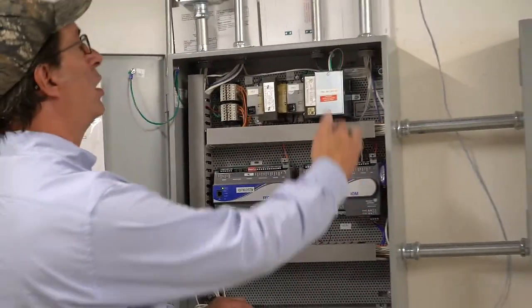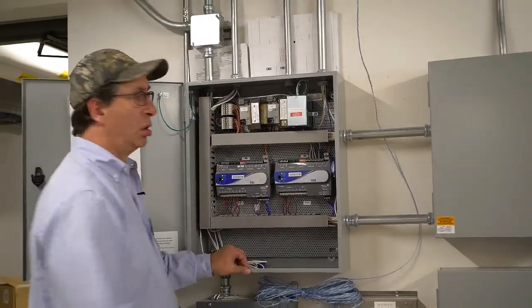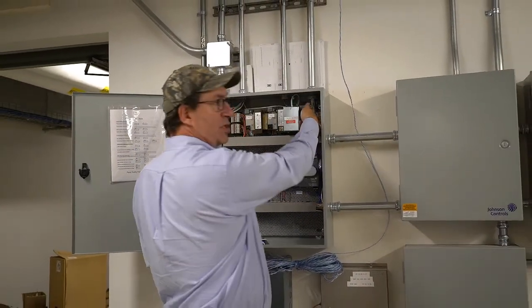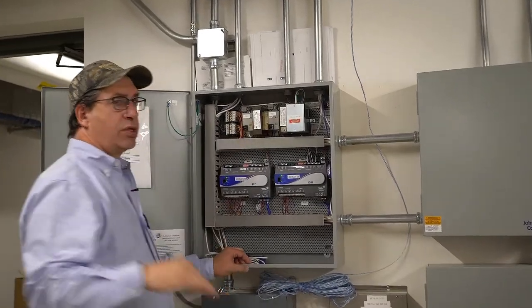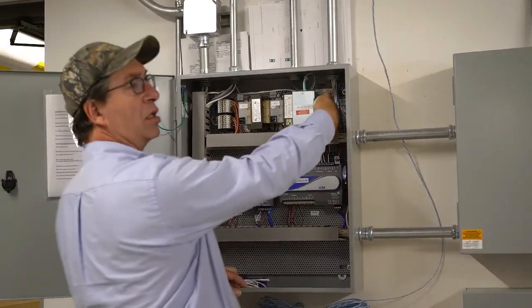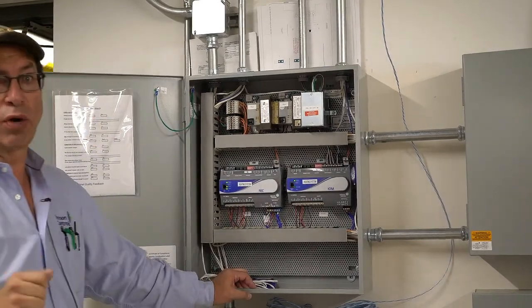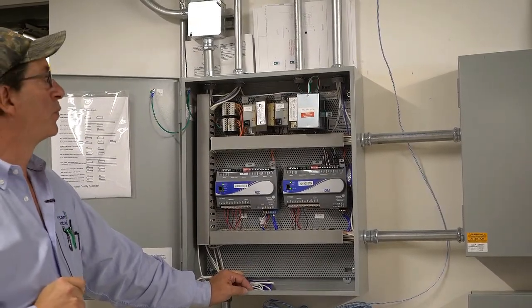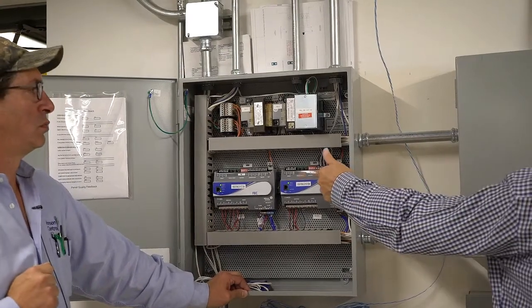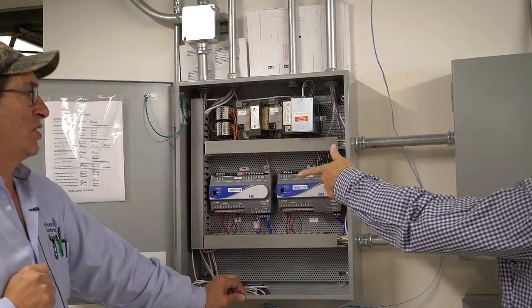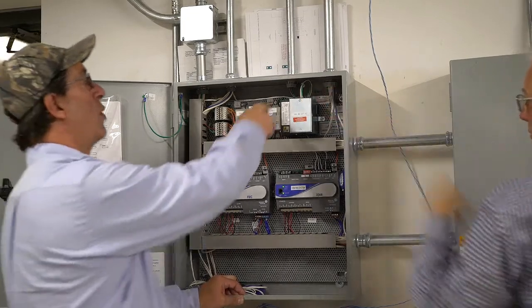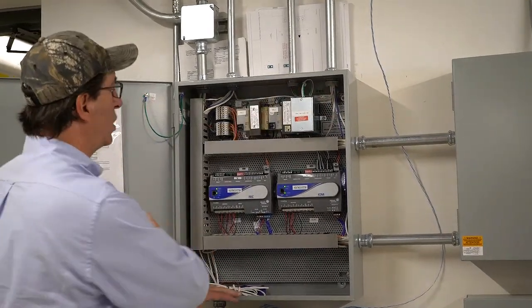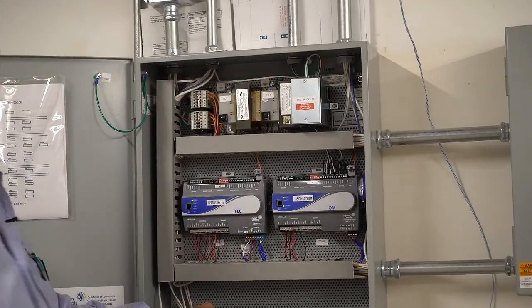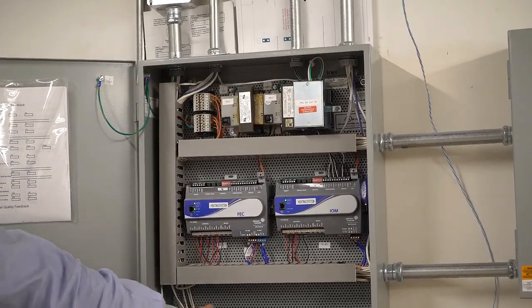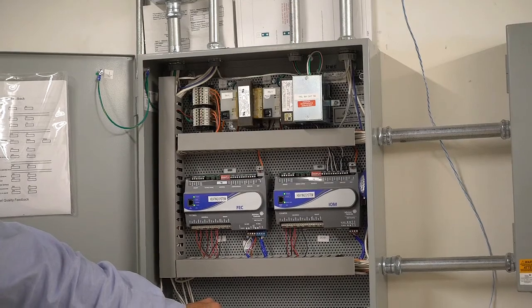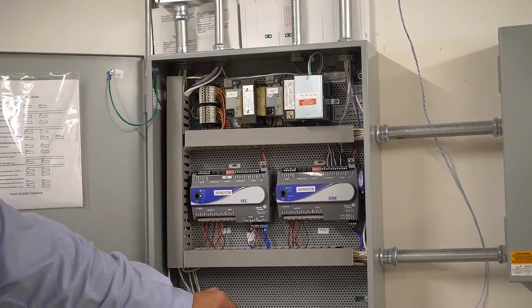Something else to keep in mind here, again, you have your rocker switch up here. There are auxiliary power outlets on the side here. If you kill this switch, that just kills the 24 volt. These outlets will stay hot unless you find the breaker and kill the breaker. Okay? So would there be an occasion where you'd ask us to remotely repower those? Yes. Then this is how we do it. Correct. I'm just going to have you shut that off, wait till all the lights go dead, and then I'll have you turn it back on. So it's like rebooting a computer. So if you say, hey, go ahead and turn it off, turn it back on, like a DirecTV box.